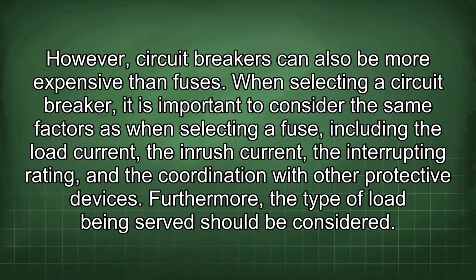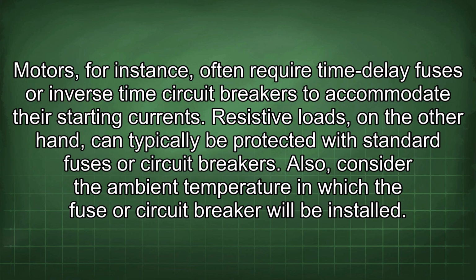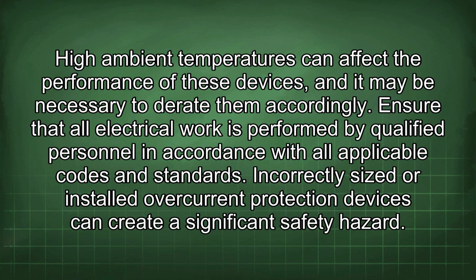Furthermore, the type of load being served should be considered. Motors, for instance, often require time delay fuses or inverse time circuit breakers to accommodate their starting currents. Resistive loads, on the other hand, can typically be protected with standard fuses or circuit breakers. Also, consider the ambient temperature in which the fuse or circuit breaker will be installed. High ambient temperatures can affect the performance of these devices, and it may be necessary to derate them accordingly.